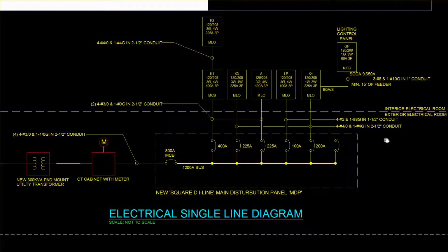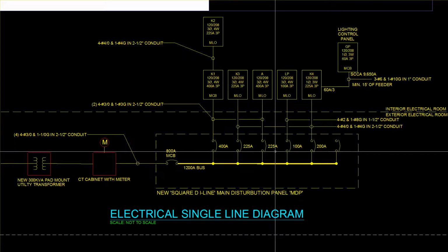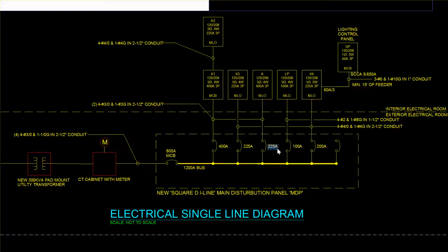Now you'll see here are all the different feeder configurations. So you'll have 2 sets of 4 3/0 and 1 number 3 ground in a 2.5-inch conduit. And that's being called out. You'll see the circles. They've been added here. So we've got the 2 situations here where these multiple sets of 3/0 are going. Now I'm just noticing a little error in my main circuit breaker here. This should be a 400. Oops. So I'll fix that now and be done with that.